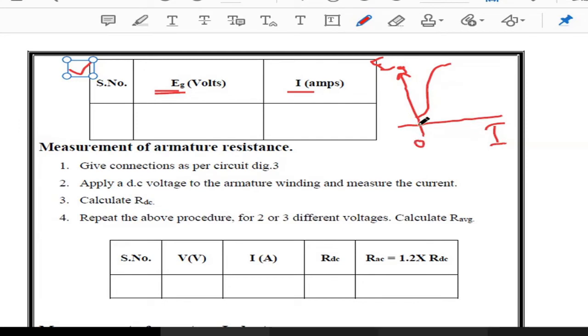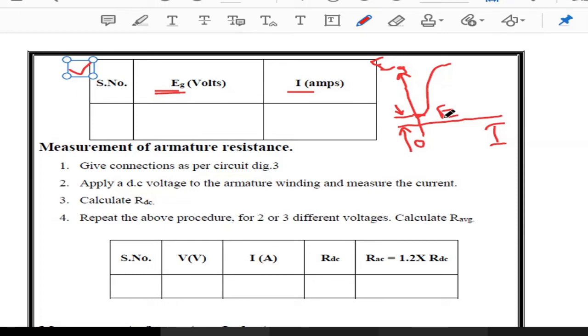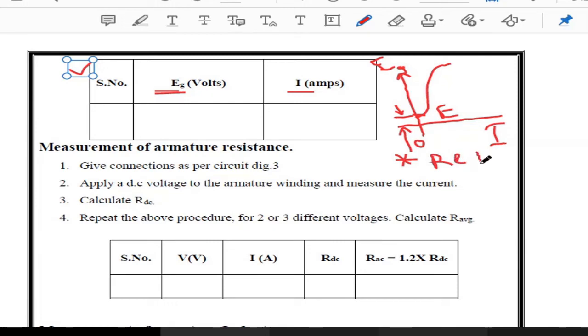Even without applying field current, we will observe some voltage on the voltmeter. The reason for this is the residual property of the machine. This voltage at zero field current is the back EMF due to residual magnetism. This is a very important concept — even when current is zero, we get some voltage due to the residual property of the DC generator.